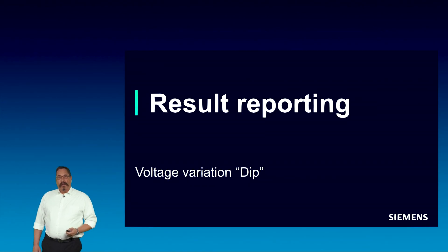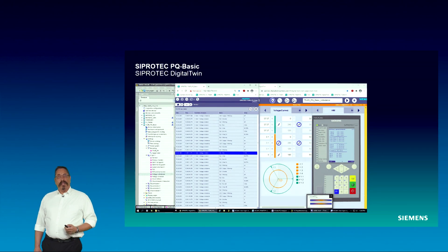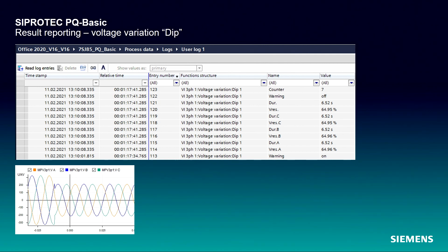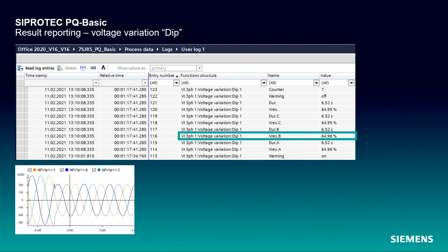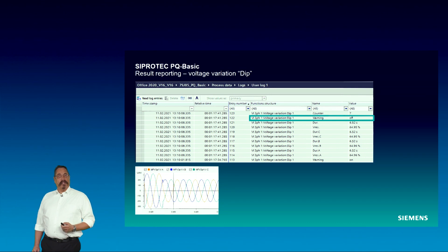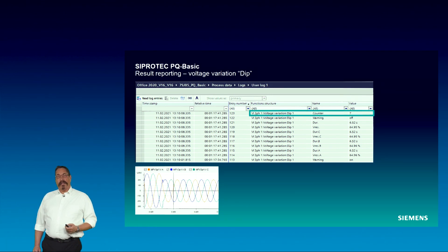Result reporting: how does the result reporting for a voltage variation look like? After finishing the parameterization, I am using the Digital Twin to visualize all the evaluation results. Let us take a look into the user log. The event of type voltage dip starts with the warning indication in the bottom line. Moving upwards, we can see all the event relevant data — for example, the residual voltage of phase B or the overall voltage dip duration. The event ends with a warning-off message and finishes with an increment of the dip counter.